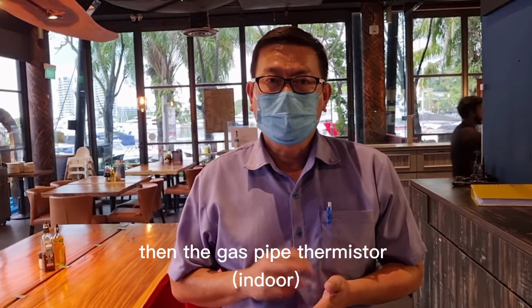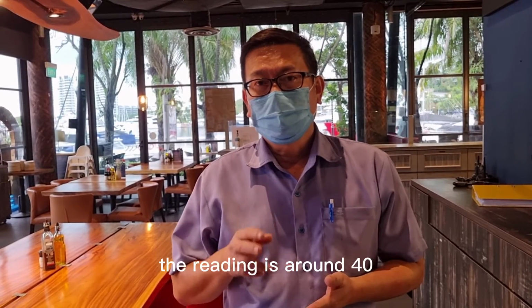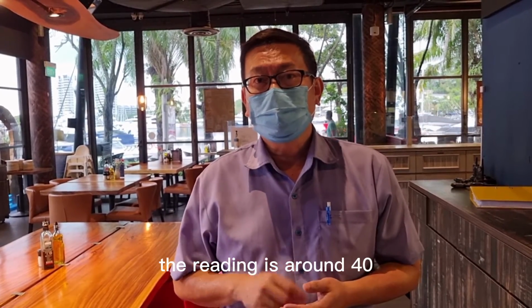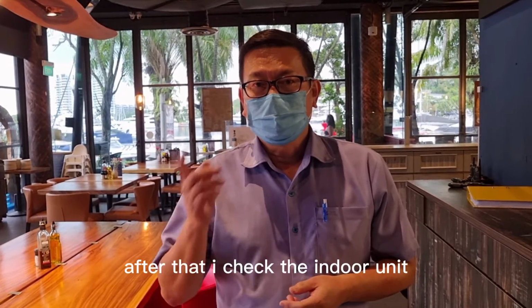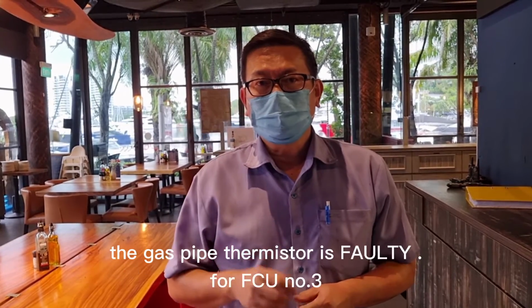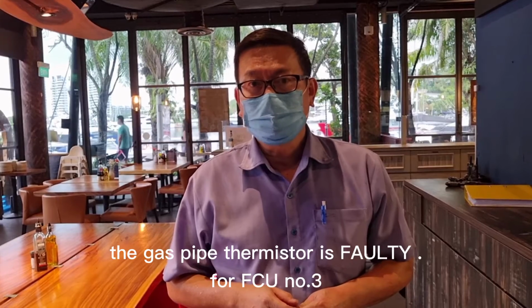Then the gas pipe thermistor reading is around 40 degrees. After that I check the indoor unit, the gas pipe thermistor is faulty, on FCU number 3, the fan coil number 3.